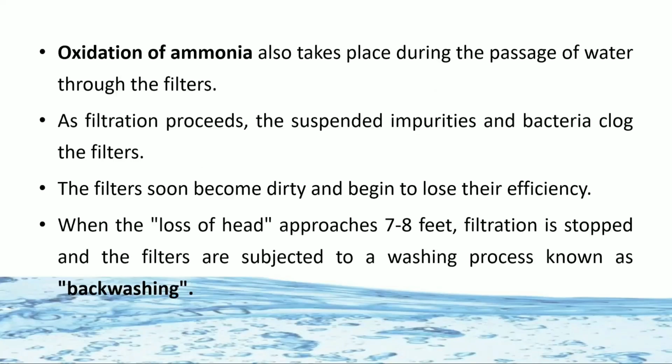When the loss of head approaches 7 to 8 feet, means the clog which is suspended in the filter reaches about 7 to 8 feet, filtration is stopped and the filter is subjected to washing or cleaning. Here, the cleaning process is known as backwashing.